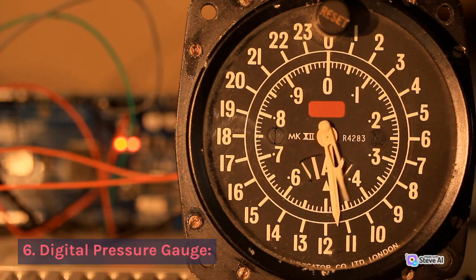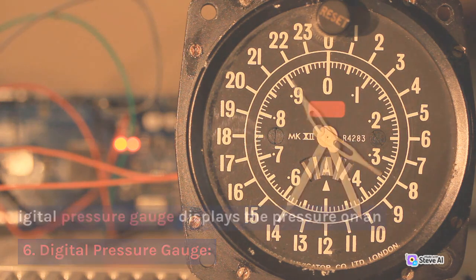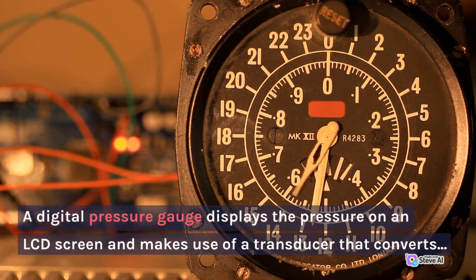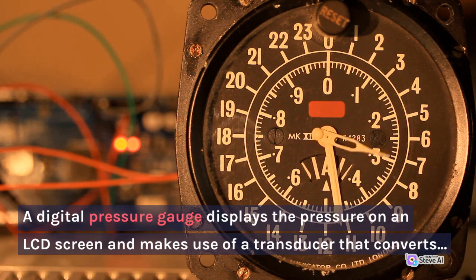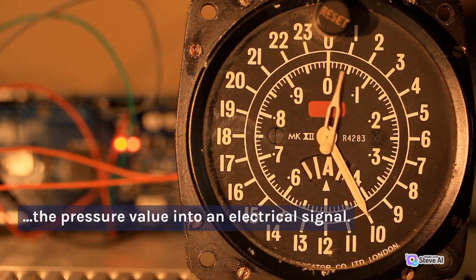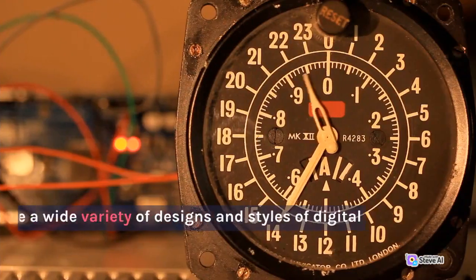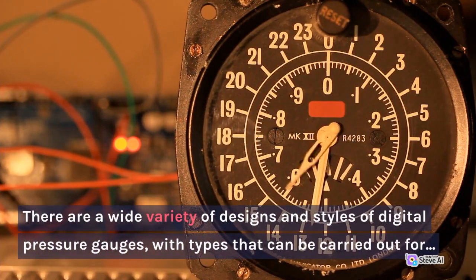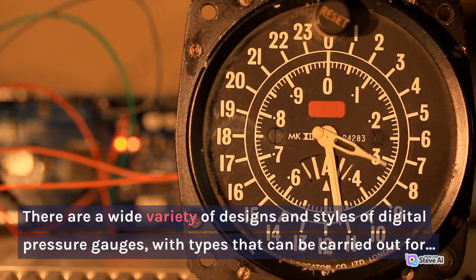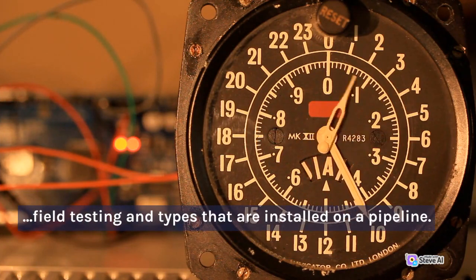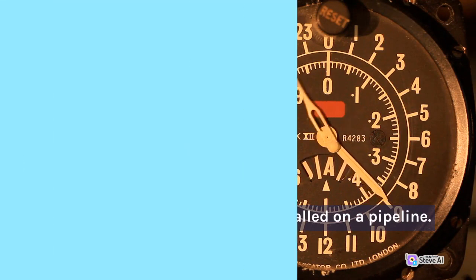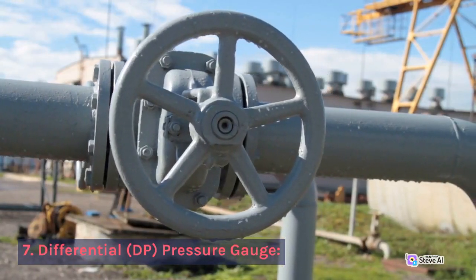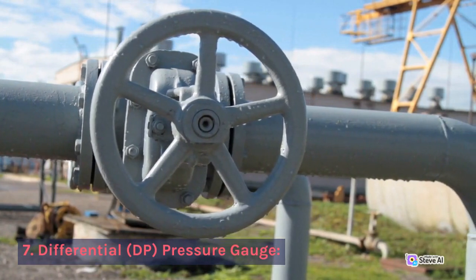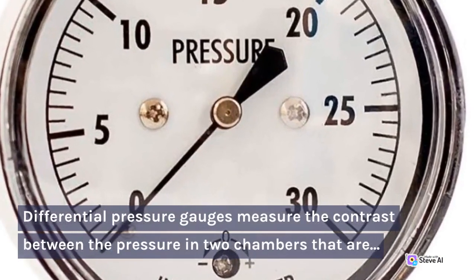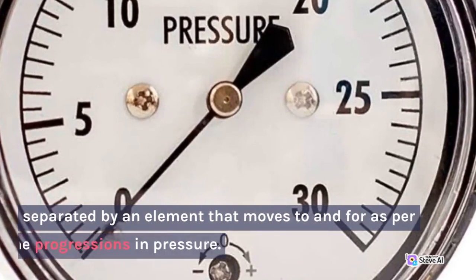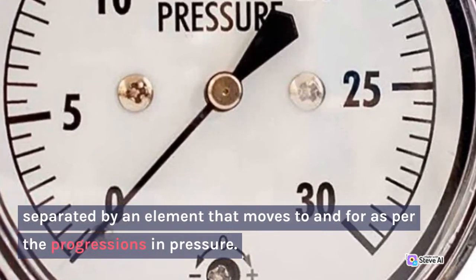6. Digital pressure gauge. A digital pressure gauge displays the pressure on an LCD screen and makes use of a transducer that converts the pressure value into an electrical signal. There are a wide variety of designs and styles of digital pressure gauges, with types that can be carried out for field testing and types that are installed on a pipeline. 7. Differential (DP) pressure gauge. Differential pressure gauges measure the contrast between the pressure in two chambers that are separated by an element that moves to and fro with the changes in pressure.